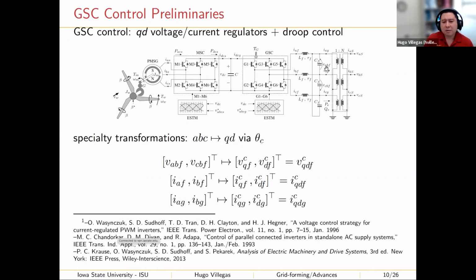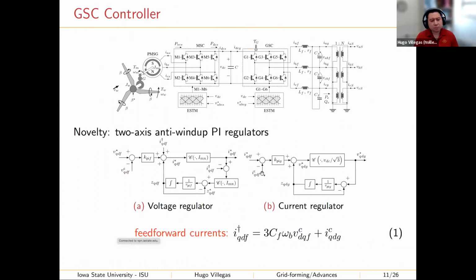So the whole idea is that, for example, during a high current impact, these currents IAG, IBG, and ICG are going to change drastically. Then the GSC can be programmed to compensate quickly for those currents in order to regulate voltage, of course within the limits of the switches that make up the grid side converter. So how did we extend this? Because these things are already standard. What we did was tackle the full ride-through capability problem.